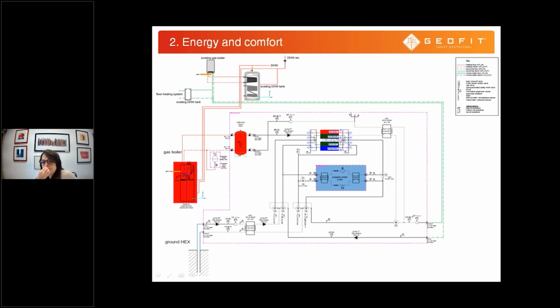The final step was to integrate what we were designing within the existing system. This is more or less the scheme we developed: here we have the ground heat exchangers, and everything in the dashed purple line is the ADS unit with the chiller, within the hybrid heat pump we developed together with Fahrenheit and the guys from CNR. We also had to introduce a gas boiler.